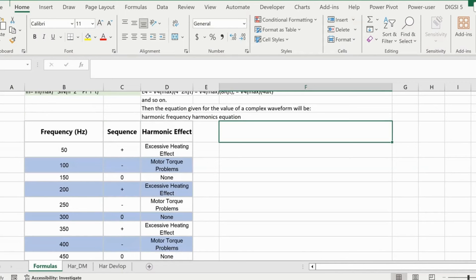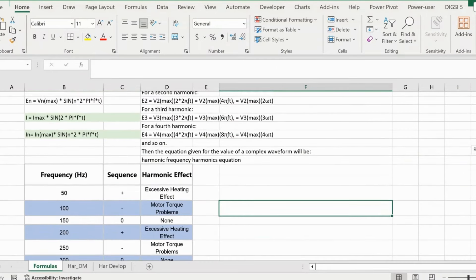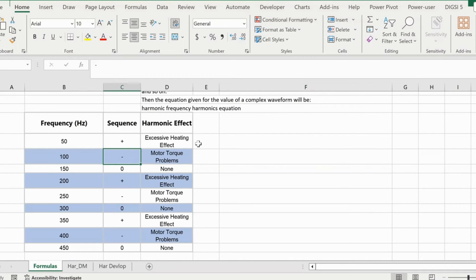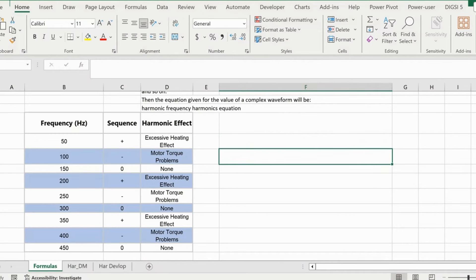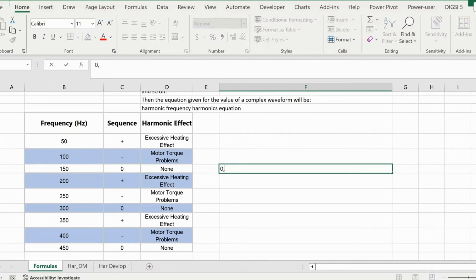The phase angle relationship for harmonics is critically important before testing any harmonic element. At 50 Hz, by default, it is a positive sequence waveform. The second harmonic at 100 Hz is negative sequence — if positive sequence is defined with balanced phase angles of 0°, −120°, +120°, then negative sequence is 0°, +120°, −120°. You must give the right phase angle to create the correct balanced fundamental-plus-harmonic waveform.